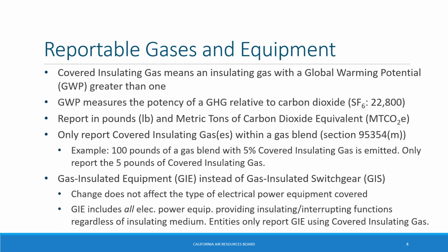The recent amendments also changed the term used to describe the electrical equipment covered by the regulation to gas-insulated equipment, or GIE, instead of gas-insulated switchgear. This change does not affect the type of equipment covered, it just clarifies that switchgear are not the only electrical equipment covered. By definition, GIE includes all electrical power equipment that provide insulating and/or interrupting functions regardless of insulating medium. The term GIE, therefore, includes, for example, equipment that use SF6, alternative gases, vacuum, and solid dielectric mediums. While these are all considered GIE, only those GIE that use covered insulating gas are required to be reported.